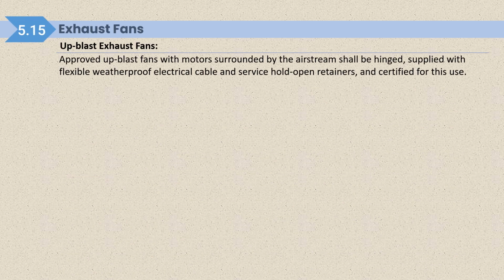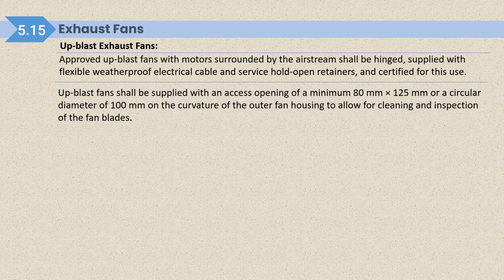Exhaust fan. There are three types of exhaust fan used in exhaust systems. One is upblast exhaust fans. Approved upblast fans with the motor surrounded by the airstream shall be hinged, supplied with flexible weatherproof electrical cables and a service hold open retainer, and certified for this use. An upblast fan shall be supplied with an access opening of minimum 80 mm by 125 mm, or a circular diameter of 100 mm, on the curvature of the outer fan housing to allow for cleaning and inspection of the fan blade.